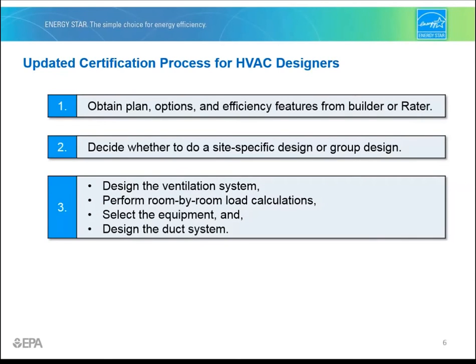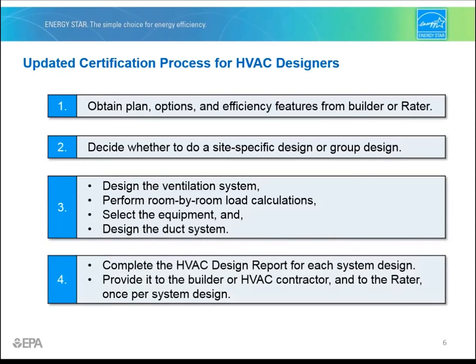Next, you'll design the ventilation system, perform room-by-room calculations, select heating and cooling equipment, and if applicable, design the duct system. Once the design is complete, just fill out the HVAC design report for each system design and hand it over to the builder or HVAC contractor and to the home energy rater, once per system design.